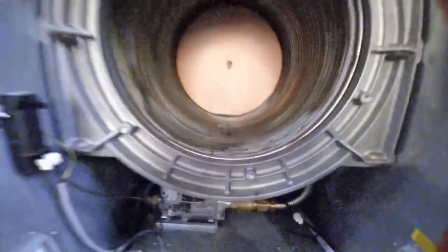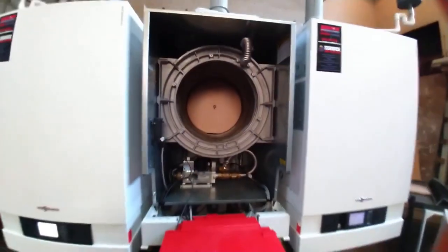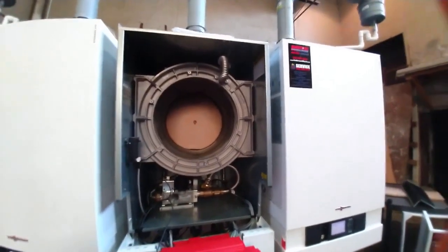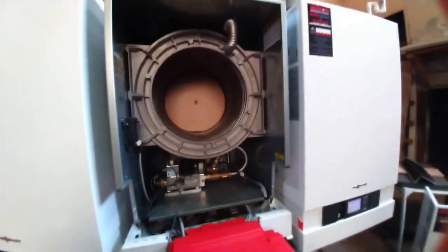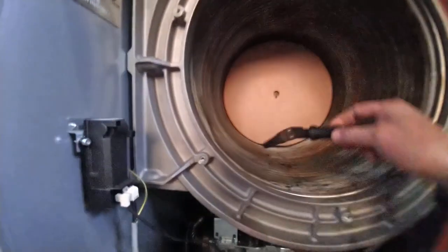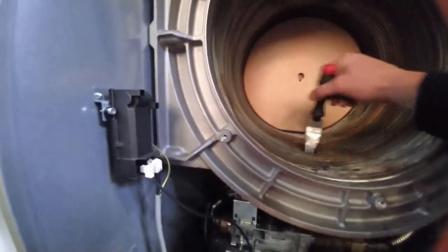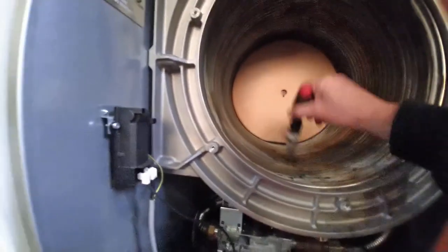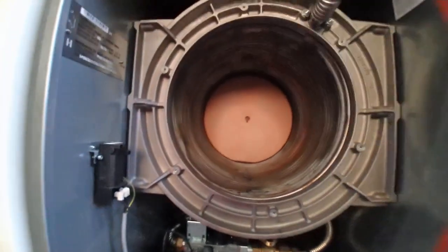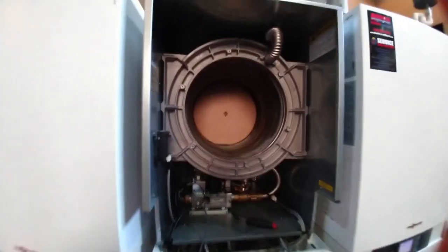tubes in here, see how much debris is here. And even when there's not a buildup on the surface, sometimes down in between you can get enough that we want to make sure that we go down there with the special tool supplied by the manufacturer to actually brush it out, clean it out, and make sure it's clear. So we're going to use this. We're going to go down between these. We're going to clean each one out, and we're going to hose it out with hot water prior to putting it back together again.